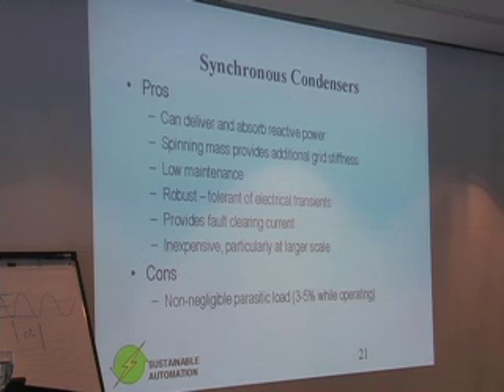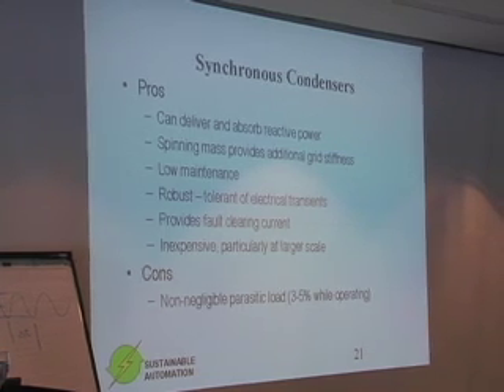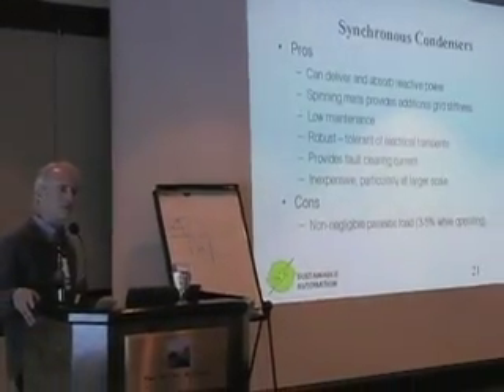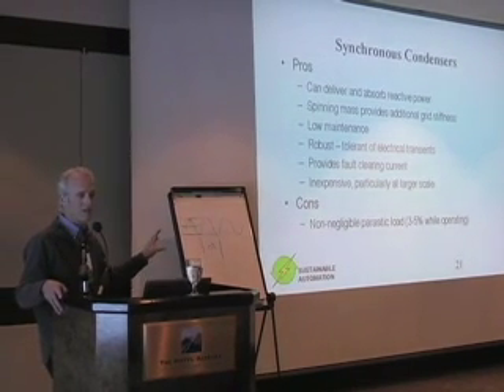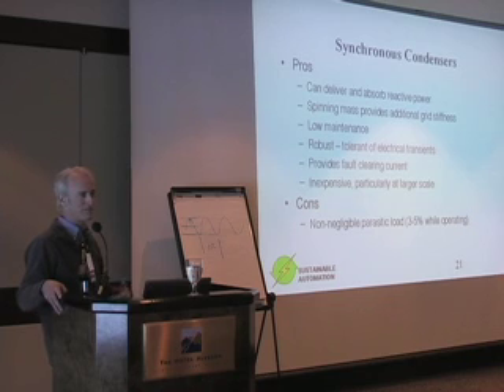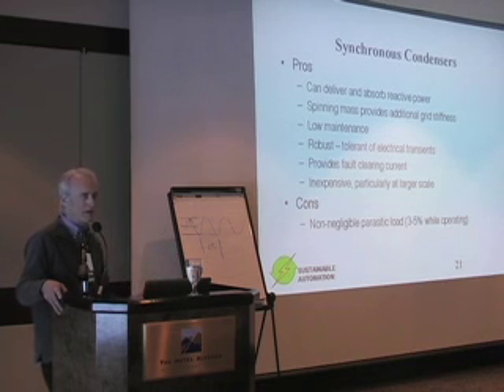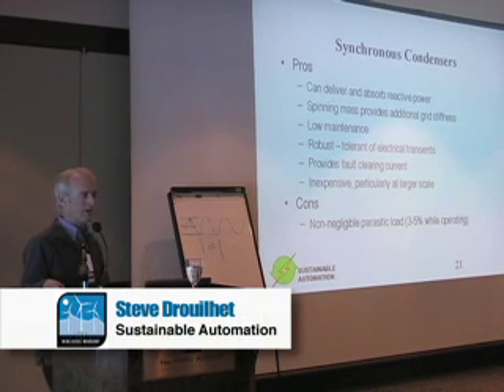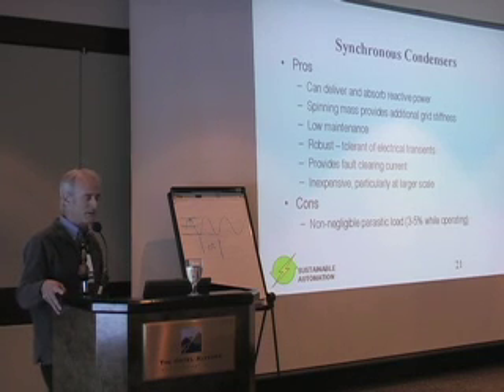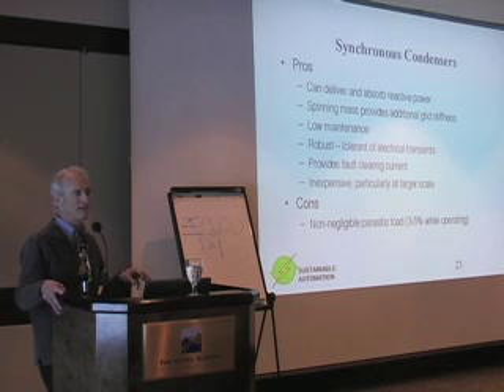Synchronous condensers are robust. It's difficult to hurt them. They're relatively inexpensive, especially as you scale up, because the controls required are essentially fixed cost, and the cost of the controls doesn't increase whether the rating is 100 kilowatts or really a kilovar, because you're rating this in terms of its reactive power delivery, all the way up to 1 megavar or more. The cost of the controls stays relatively constant. Obviously, the size of the wire and the breakers and the contactors all goes up. But the controls themselves, which represent a considerable fraction of the cost on the smaller system, don't represent much cost on the larger system.